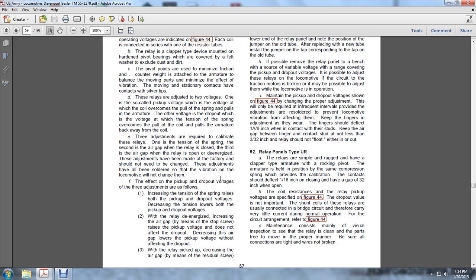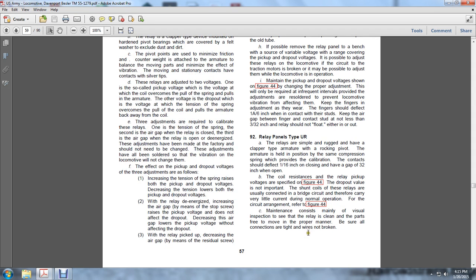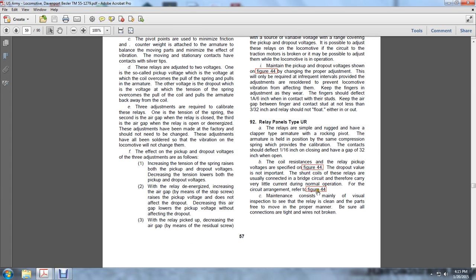The shunt coils of these relays are usually connected to the bridge circuit, therefore carrying very little current during normal operation of the circuit arrangement. Refer to figure 49 and figure 44. Maintenance consists mainly of visual inspection to see if the relay is clean and the parts are free to move in the proper manner. Make sure all connections are tight and wires are not broken.